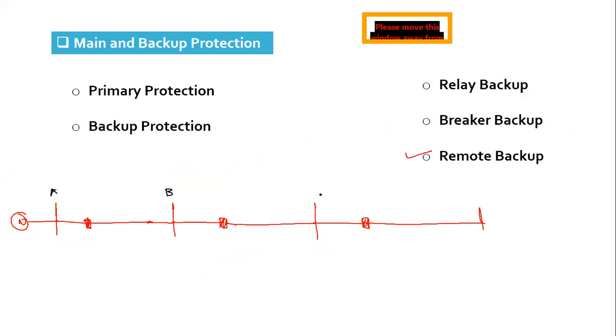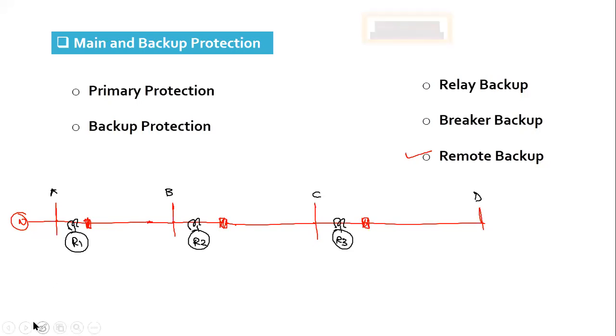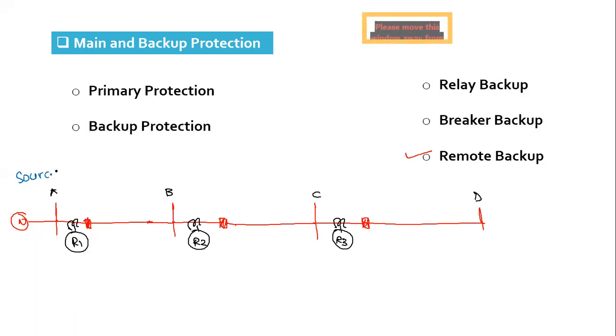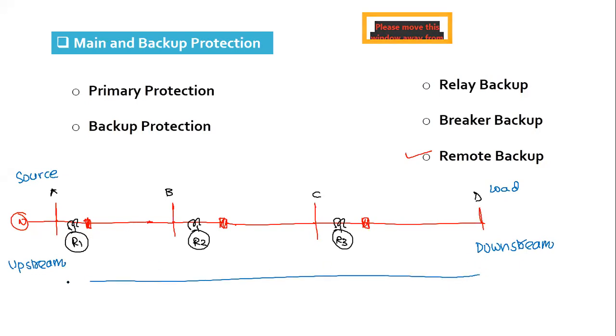Substation A, B, C, D. Okay, R1, R2 is the relay set at substation B, R3 is the relay set at substation C. So this is the source side, and this is, let's say, the load side. So this is called the downstream, and this is called the upstream. Okay, if we move from load to source, we call it upstream, and if we move from source to load, let us call it downstream.